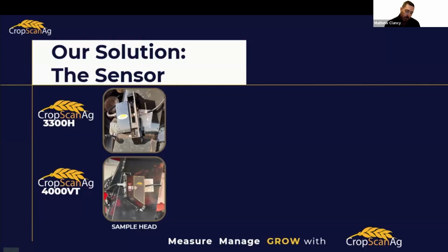Because if you really look at what we're doing there, we're taking grain off the paddle that's going at a very high frequency, and we're feeding it into the chamber at, it's not 45 degrees, but let's say a 30-degree angle. We're trapping it. We're taking the scan and doing that. So really the straightness of the sample head is key to maintain grain flow and avoid blockages. Okay, so the sharper that 3300H sample head is, the better.